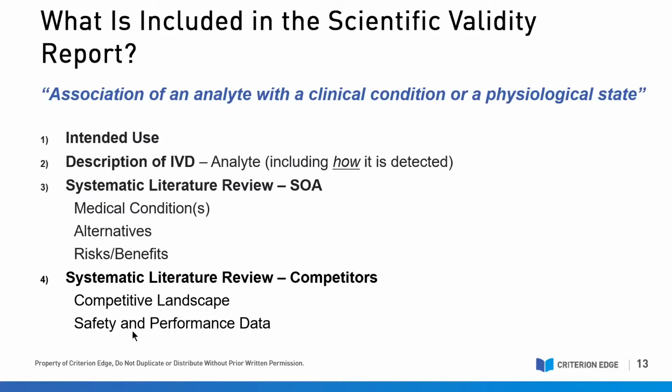So as you're beginning to develop your template, ask yourself if your SVR includes all IVDR required elements. A great advantage would be if you had a template that's already been pressure tested by having gone through a notified body review. But IVDR is new to everyone, so it's really just hypothetical whether or not your template will pass notified body scrutiny. Having experience with MDR and CER preparations will be extremely helpful as you develop these templates. As you go along the process of developing these templates, ask yourself if it flows. Is it logical, and does it tell the story of your IVD?